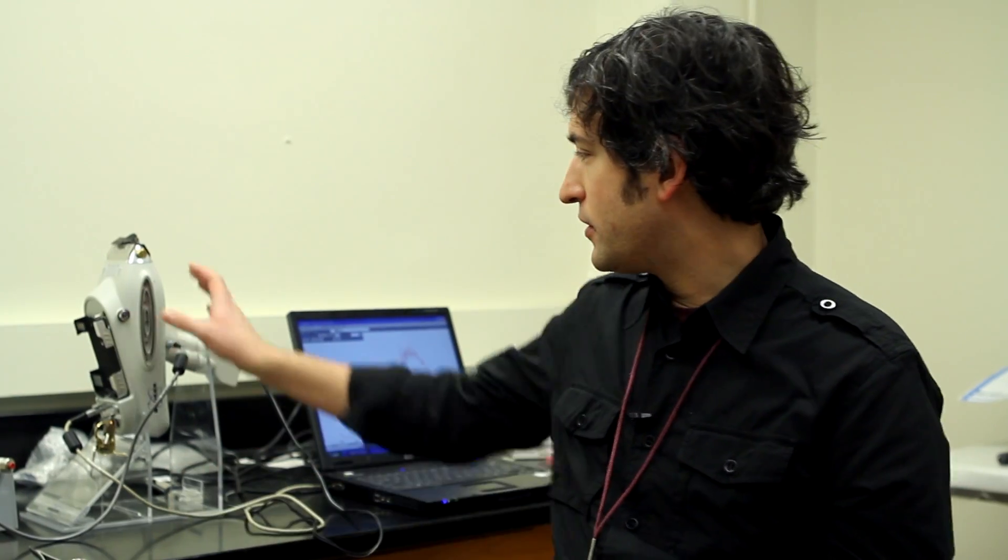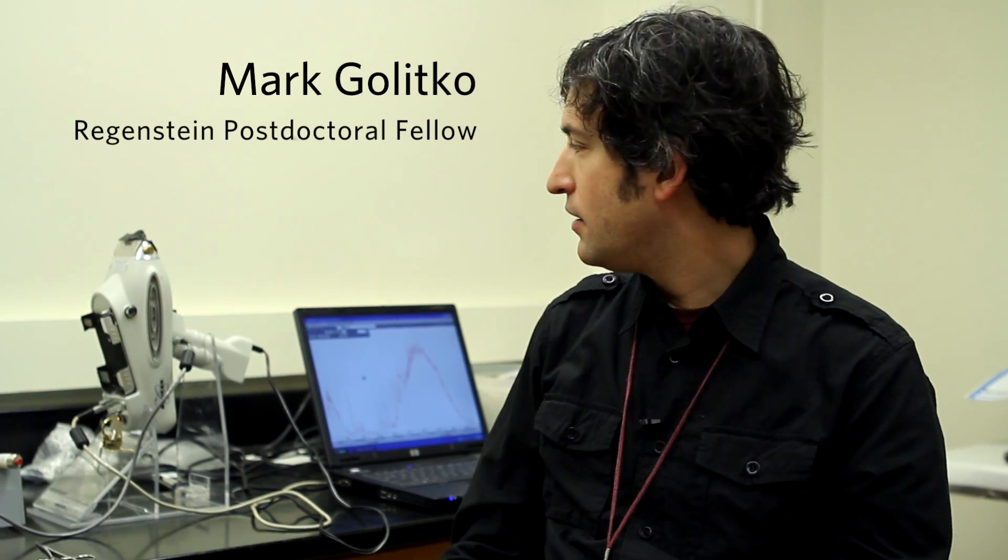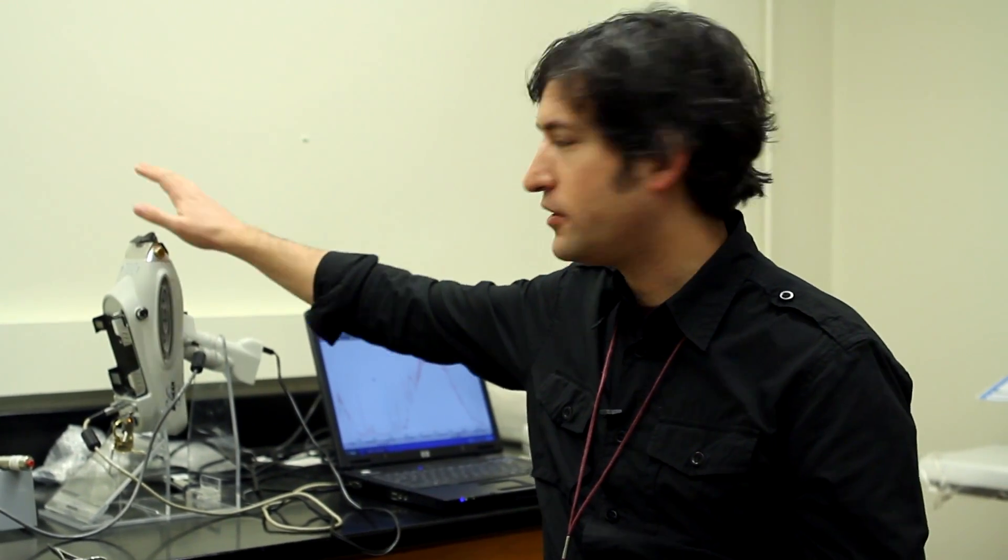Basically the way it works is that within the gun here there's actually an x-ray tube similar to what you would have at a dentist to x-ray your teeth. And it actually emits x-rays upwards like this under the sample which is then sitting on top here.